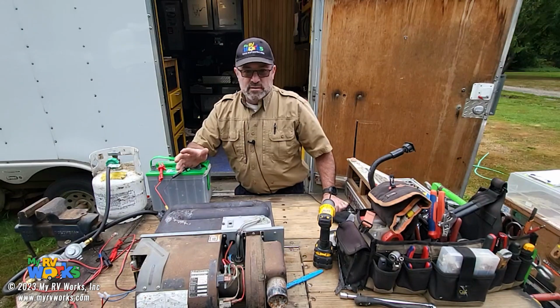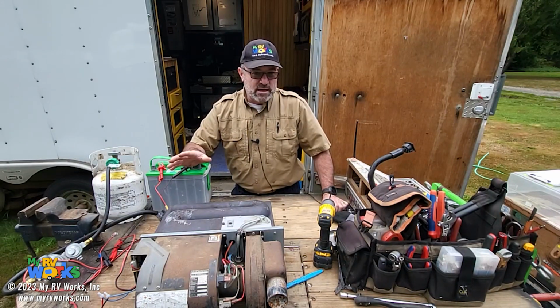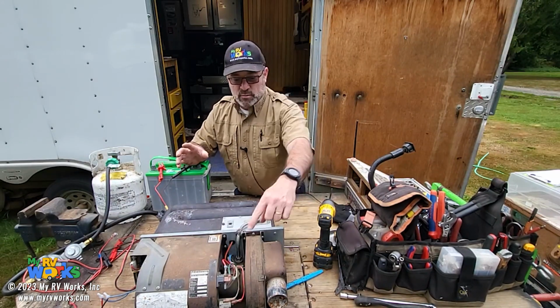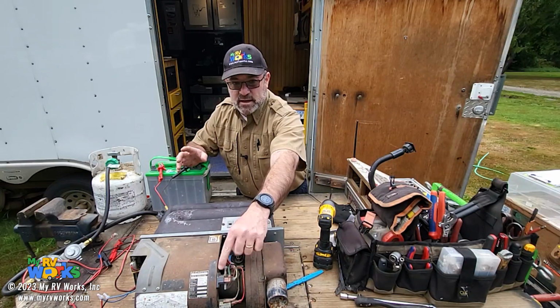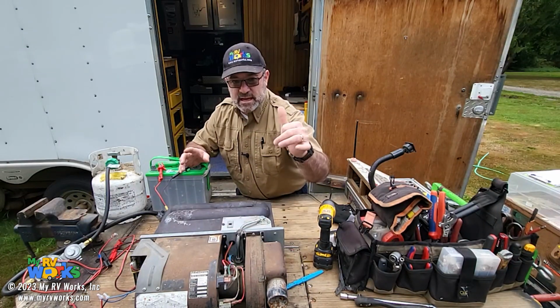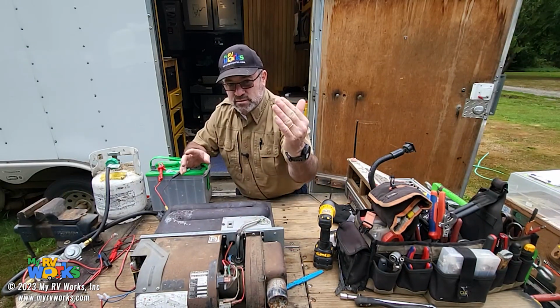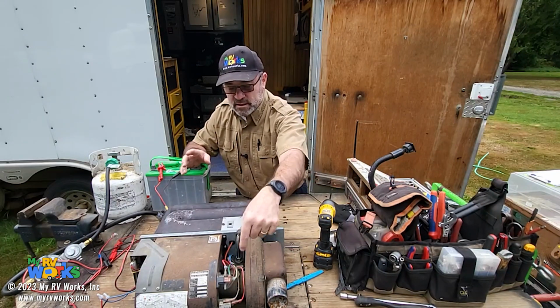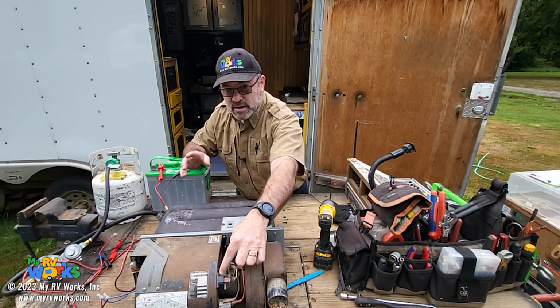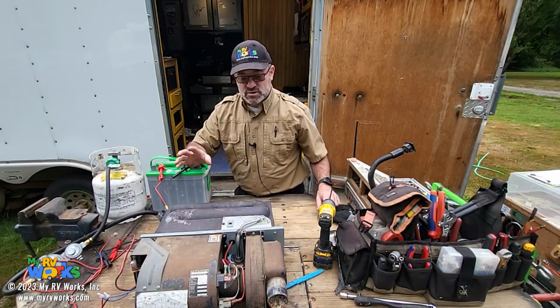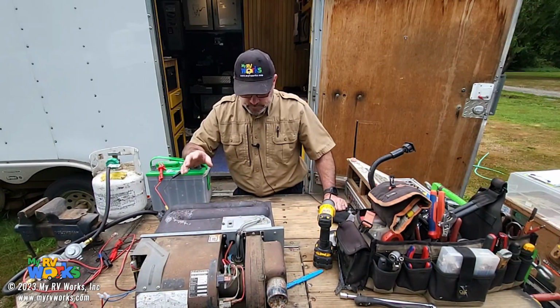It's going to go through typically around a 90-second cool down, called a post-purge. What we're doing is waiting for this relay to cool itself down, and then the little tin-can bimetallic part inside will cool down, and the little metal thing will flip open, opening our circuit. This relay right here is what's controlling the fan motor, okay?